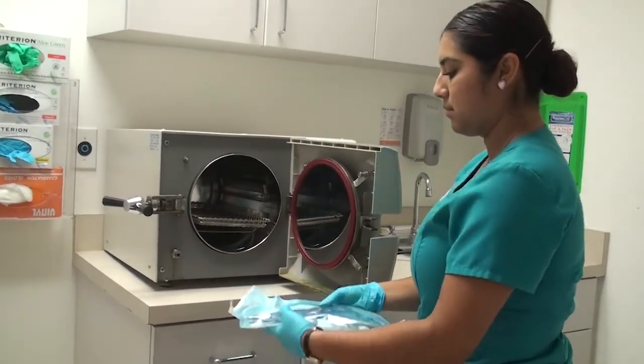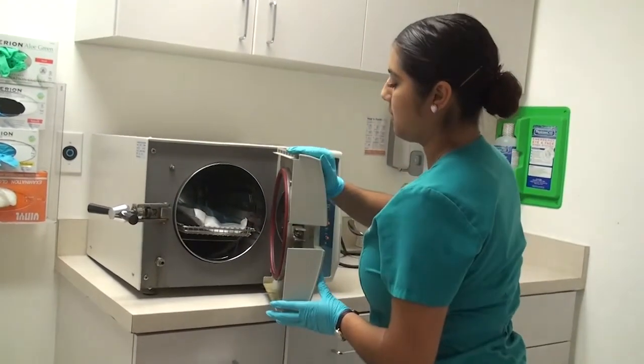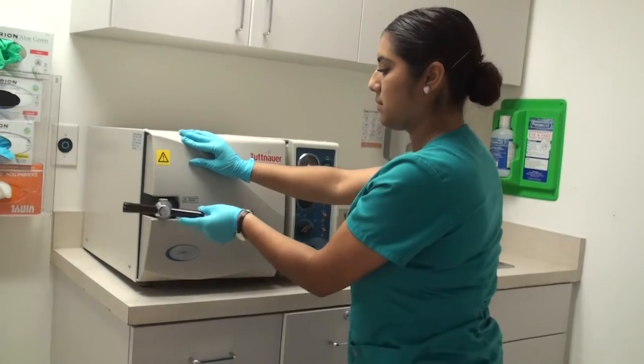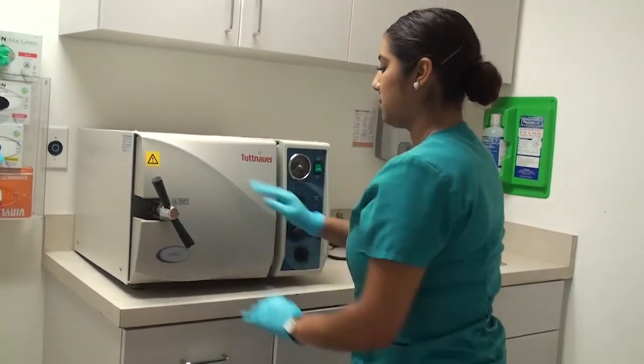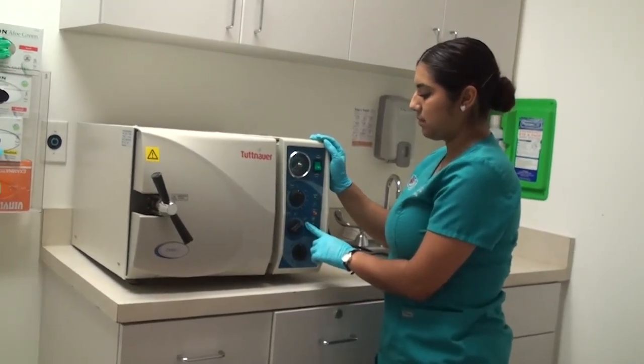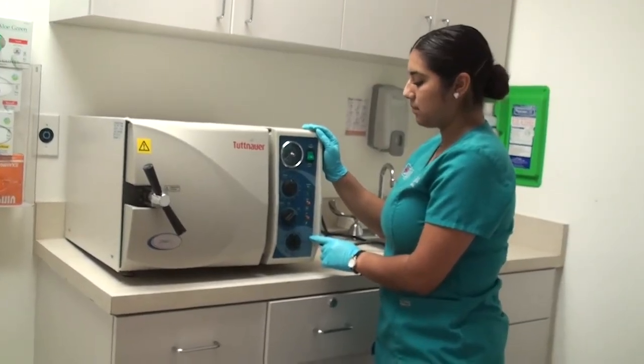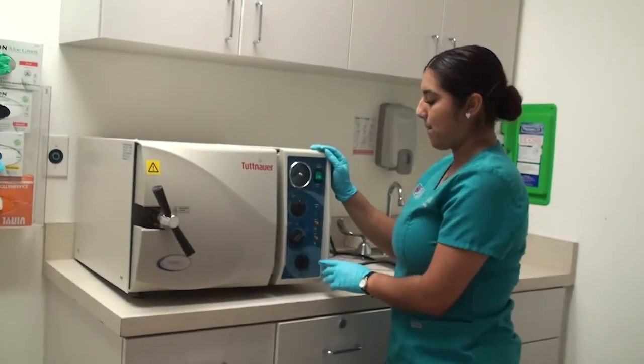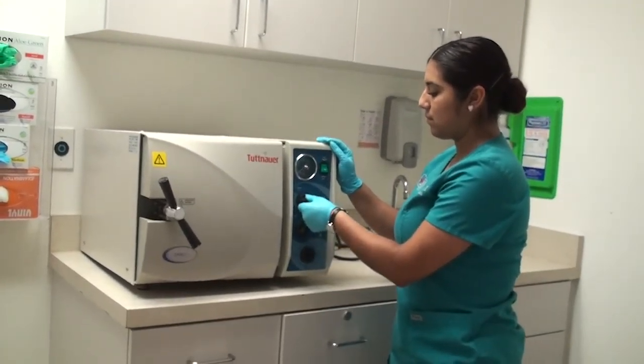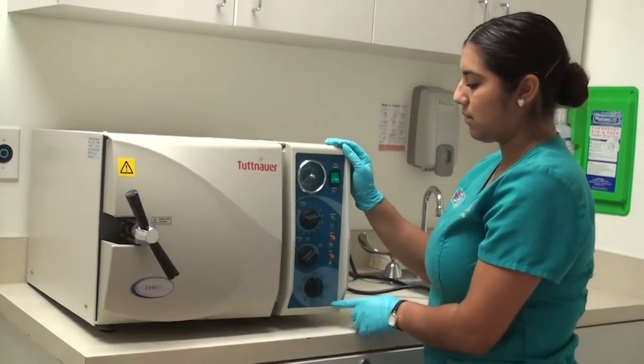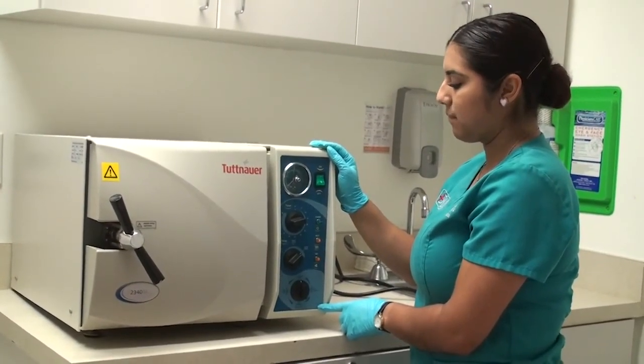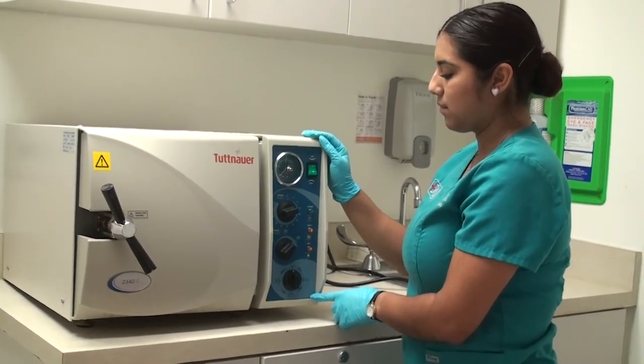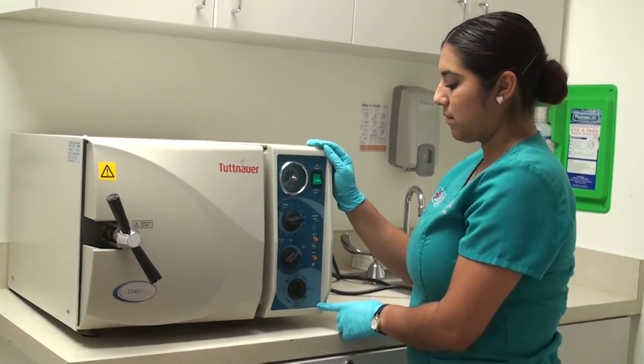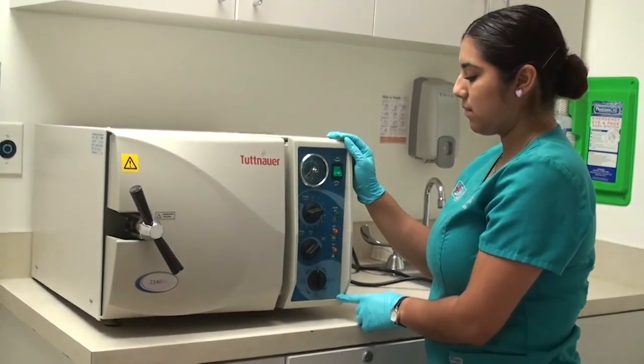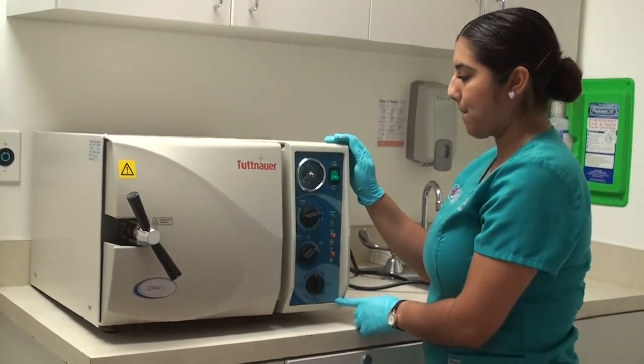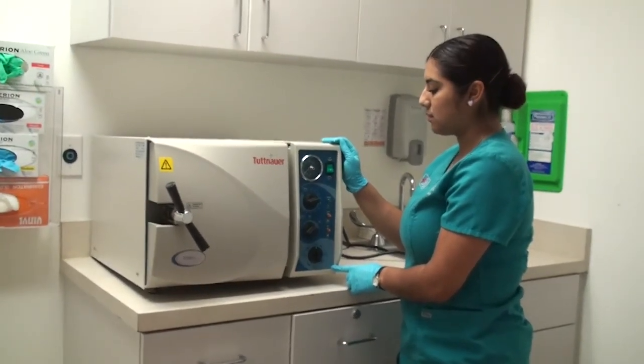Now that you have the handpiece and cord unit in your sterilization pouch, it is time to put it in the autoclave machine. On the autoclave machine, you would set a suitable temperature. We recommend a minimum of 135 degrees Celsius or 275 degrees Fahrenheit for a duration of 15 minutes. However, you can also use whatever sterilization quality parameters you have as a standard in your area. You can also use the color indicator on the back of your sterilization pouch. Make sure that the indicator turns into the color that indicates the unit has been adequately sterilized. Also, this handpiece unit can be sterilized using ionized gas, also called plasma sterilization. The plasma sterilization is performed following the sterilization protocol standards that apply to your system.